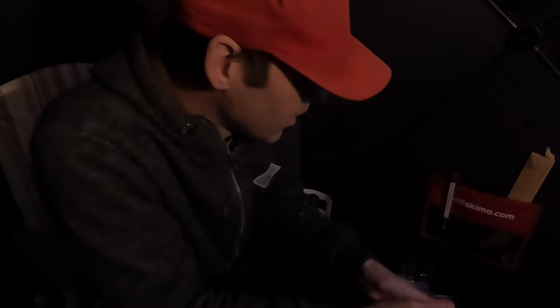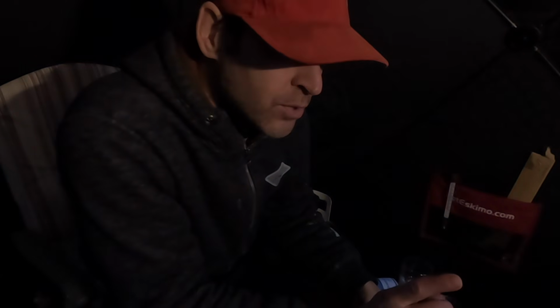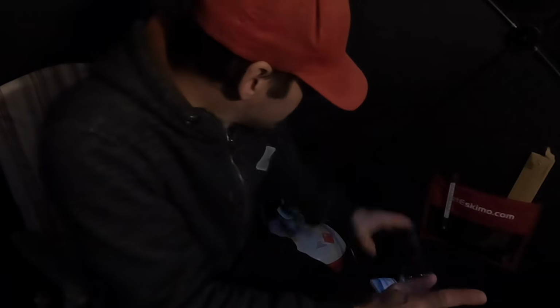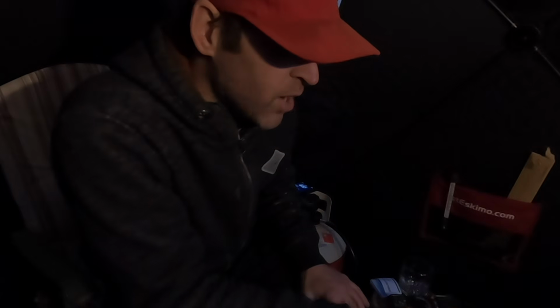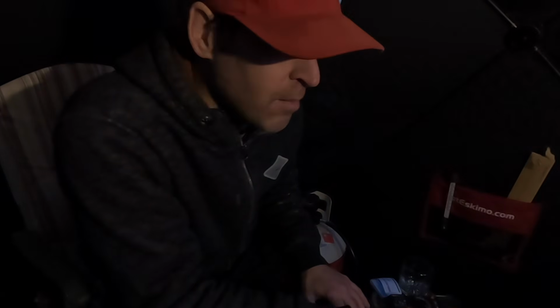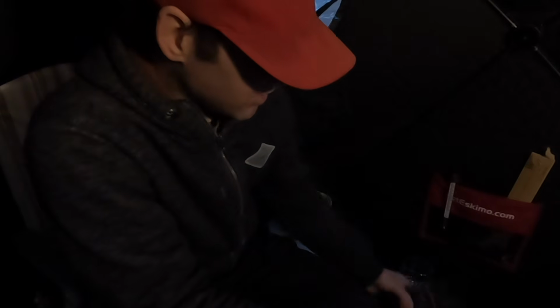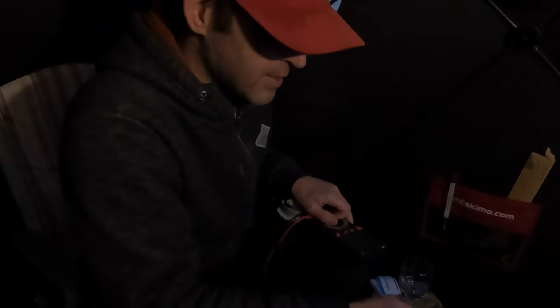All right folks, an hour has passed since I turned on the heater. It's 4:56, so around an hour. We're now going to check the temperature of the exchanger inlet and outlet, try to collect some water, and recheck the carbon monoxide. The temperature in here is about 21 Celsius, and I've had the flap on the tent partly open. First thing I'm going to check is the inlet temperature.